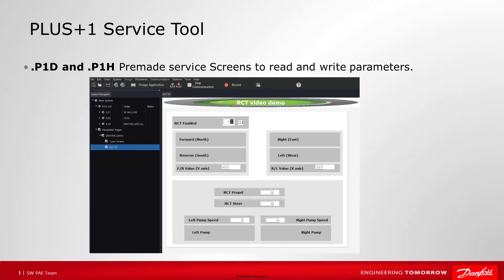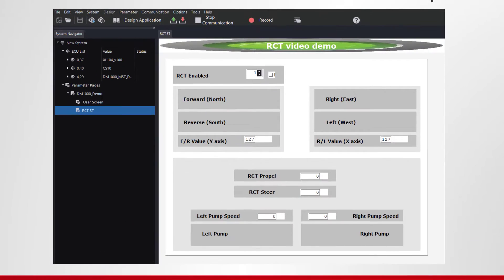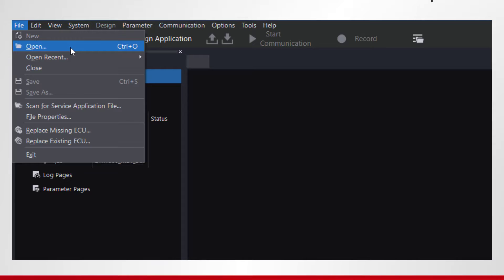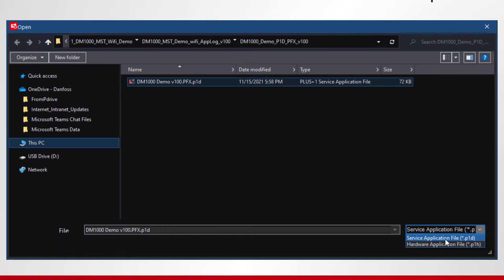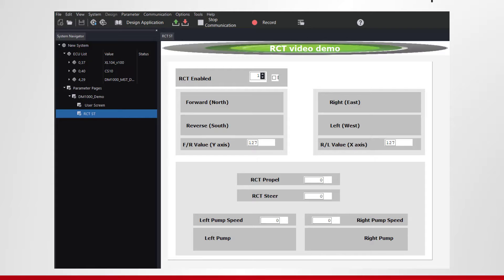Some other common files are P1D and P1H files. These are pre-made service screens that allow technicians to read and write parameters to a controller. To use a P1D or P1H, on the top menu click on File, then Open. In the file browser, select the file type and the file you want to open. After it is loaded, in the left panel you will see more pages under parameter pages. These pre-made pages will allow you to read and write parameters.